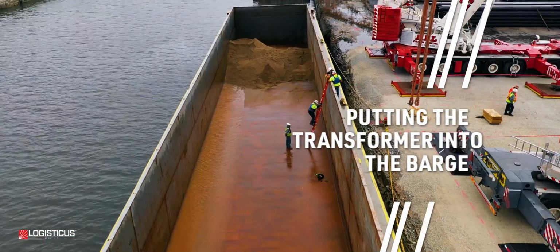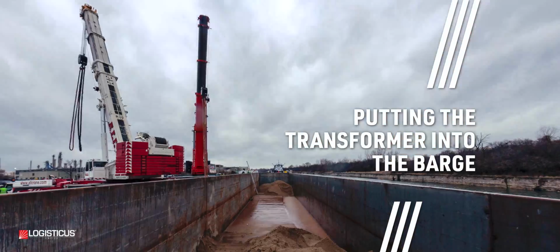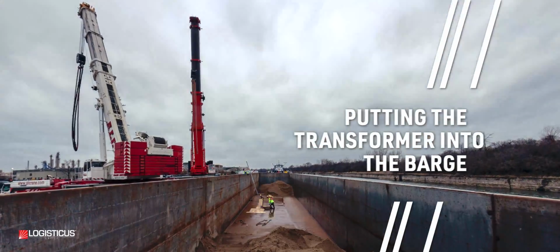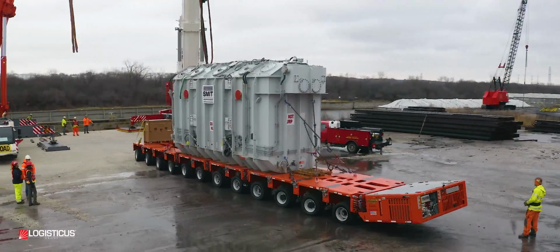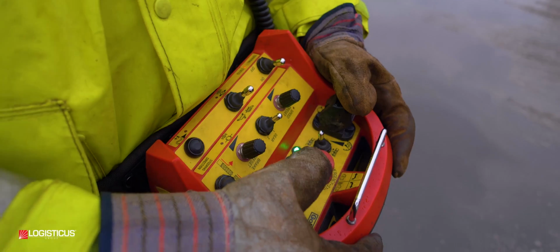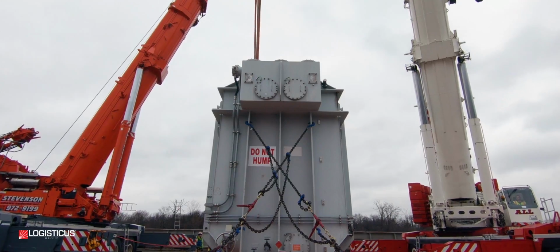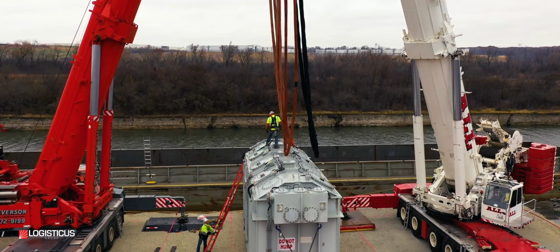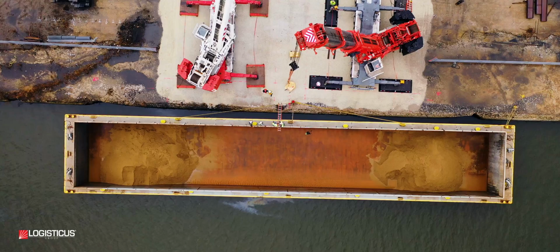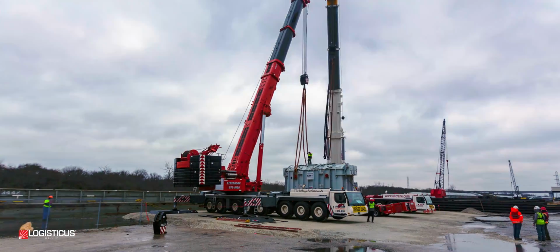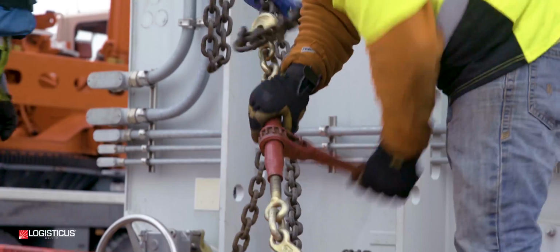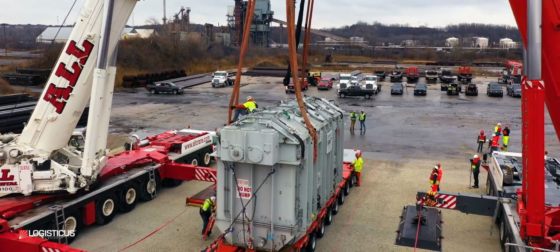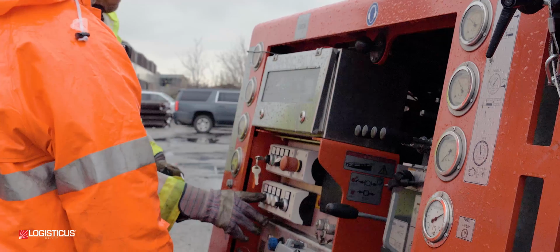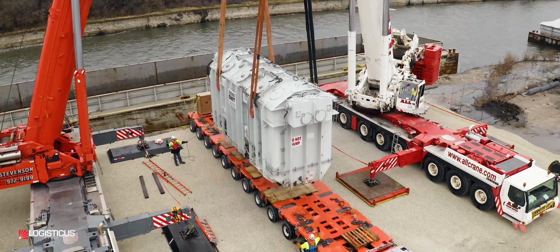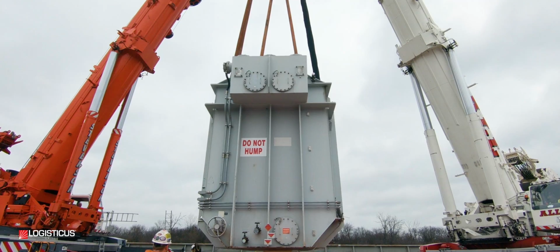The next challenge was to get the transformer from the 12-line ADD Goldhofer into a barge to be carried down the river. The transformer is so heavy that had we simply lowered it into the barge, it could have capsized. So we first loaded the barge with 600 tons of sand to ensure stability. The sand also helped to lower the barge's height above water to get under low city bridges and keep the barge balanced while underway. This was a unique feat of marine engineering.